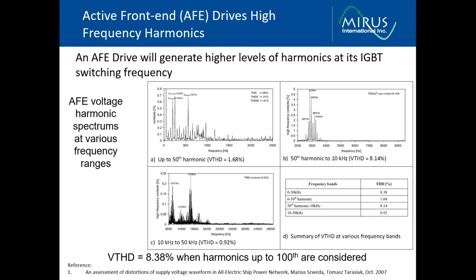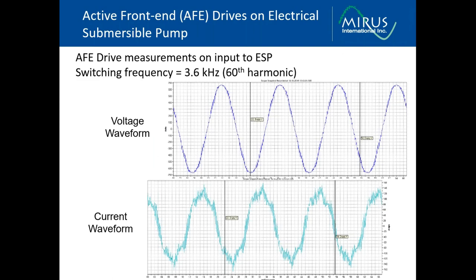In a third example of an active front-end drive, this was measurements taken on an electrical submersible pump in an oil field. You can see very clearly in the voltage the high frequency ripple. This was measured to be 3.6 kilohertz or 60th harmonic, which was the switching frequency again of the input IGBT inverter. And you can see the high frequency in the current as well.